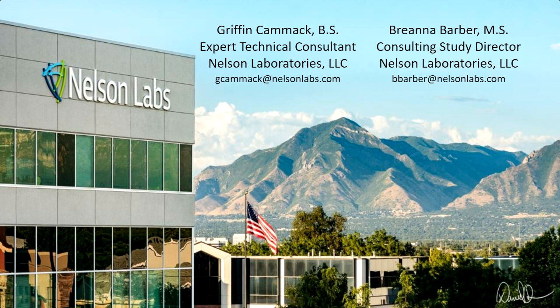In terms of point of use processing, that typically refers to the initial processing steps to not allow contamination on the device prior to the full cleaning and disinfection or sterilization procedure. Those point of use processing procedures are not typically validated or a part of the validation process. Really, you're focusing on just the cleaning process and the sterilization and disinfection process without the aid of that point of use processing step.